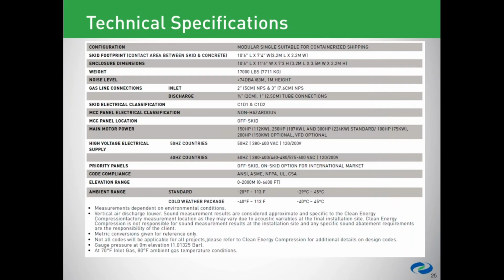And I believe I have one more here from Roberto. VFD versus line starter, which is the ballpark figure of percentage energy savings? So we don't offer a line starter. Our standard offering is a soft starter, and so I can't speak to that direct comparison. But the benefit of a frequency drive is on the starting operation, it reduces the current inrush to the motor, whereas a soft starter may get up to 4.5 times the full load amperage, a frequency starter can reduce that to about 2 times.